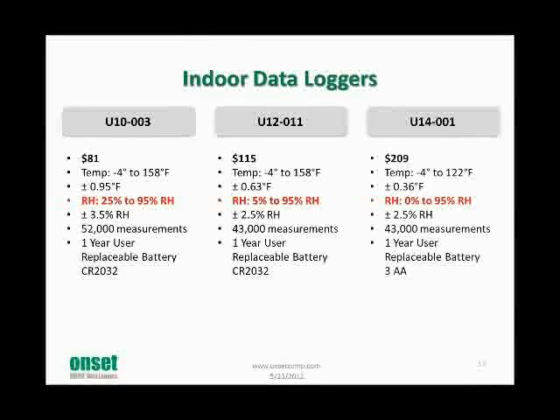And then we have the U14, the one with the display here. This has our best accuracy at under half a degree at 0.36 Fahrenheit, and again 2.5% RH, and this is going to cover the full range. Although the sensor will go up to 100%, this particular logger can't get wet, so you don't want to put it into a condensing environment.